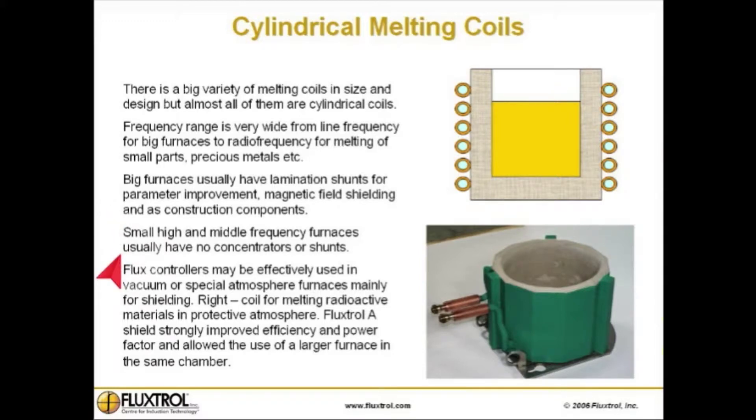Small high and middle frequency furnaces usually have no concentrators or shunts. Flux controllers may be effectively used in vacuum or special atmosphere furnaces mainly for shielding. To the right we see a coil for melting radioactive materials in a protective atmosphere. Fluxtrol A shield strongly improved efficiency and power factor and allowed the use of a larger furnace in the same chamber.